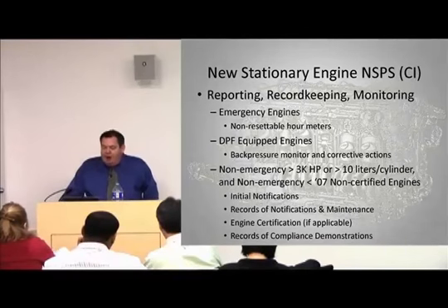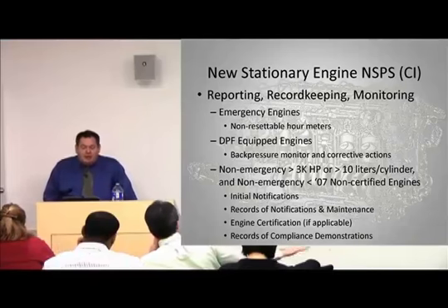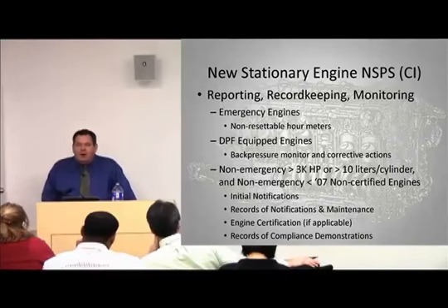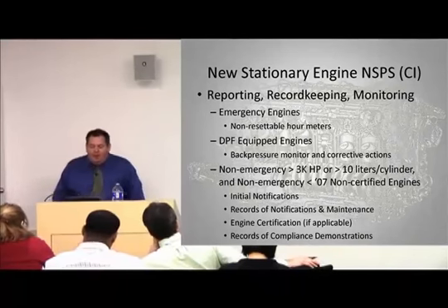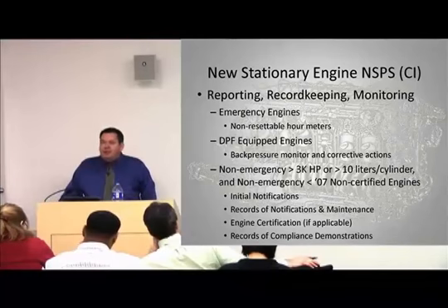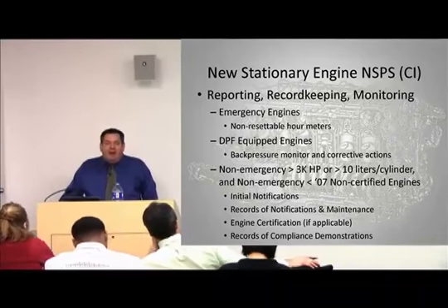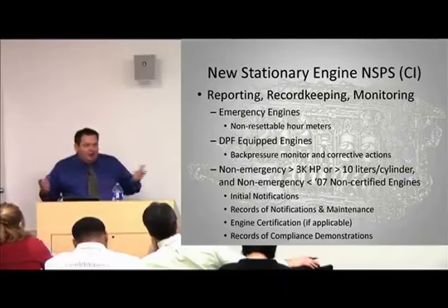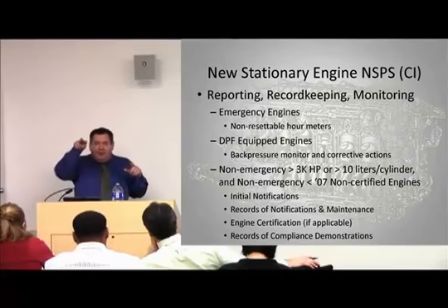Reporting, record keeping, and monitoring. No job is done until the paperwork is complete. Emergency engines, obviously we're going to keep copious records from a non-resettable hour meter. DPF equipped engines, diesel particulate filters, you have to have a back pressure monitor and you have to document corrective actions. I told you earlier about catalysts, they're flow-through devices.